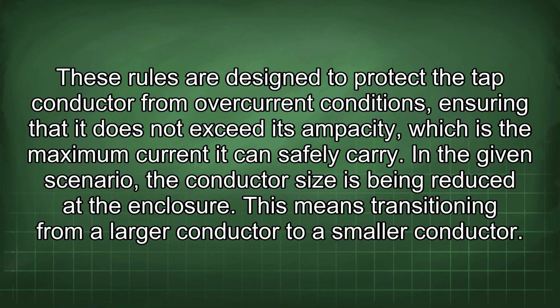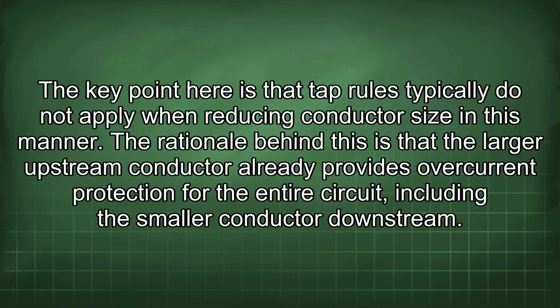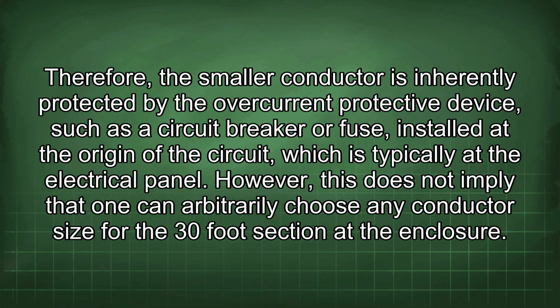In the given scenario, the conductor size is being reduced at the enclosure. This means transitioning from a larger conductor to a smaller conductor. The key point here is that tap rules typically do not apply when reducing conductor size in this manner. The rationale behind this is that the larger upstream conductor already provides overcurrent protection for the entire circuit, including the smaller conductor downstream. Therefore, the smaller conductor is inherently protected by the overcurrent protective device, such as a circuit breaker or fuse, installed at the origin of the circuit, which is typically at the electrical panel.